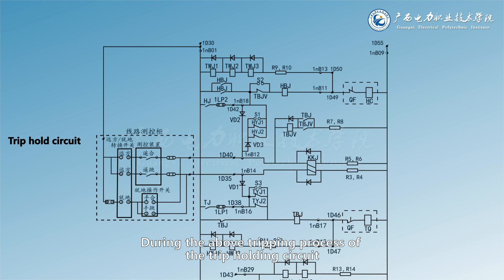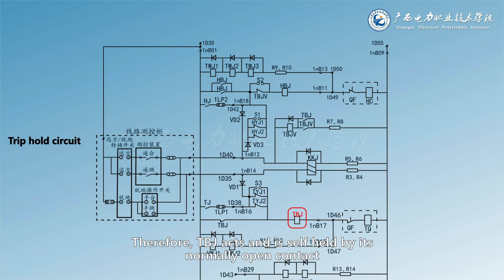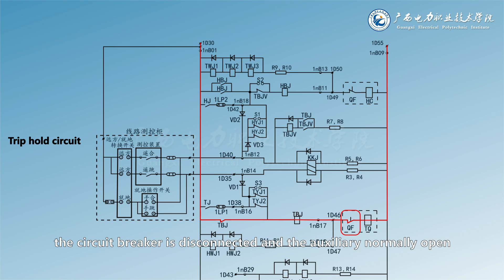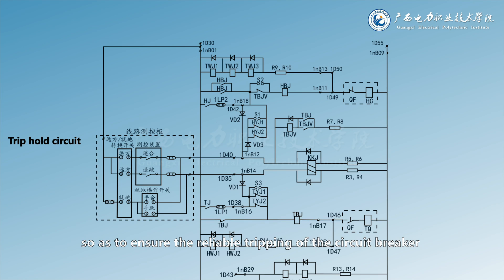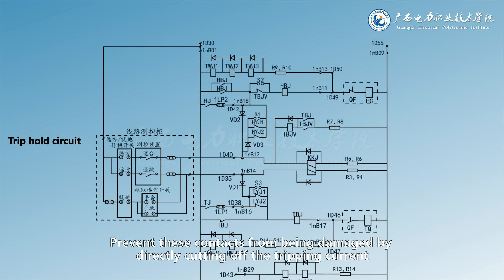During the above tripping process, whether manual tripping or automatic tripping of the protection device, the tripping current will flow through the coil of the trip holding relay TBJ. Therefore, TBJ acts and is self-held by its normally open contact. The tripping current can flow from the normally open contact of TBJ to the tripping coil of the circuit breaker until the main contact of the circuit breaker is disconnected and the auxiliary normally open contact is also disconnected. This ensures reliable tripping of the circuit breaker and protects the contacts of local operation switches, measurement and control devices and protection devices from damage caused by directly cutting off the tripping current.